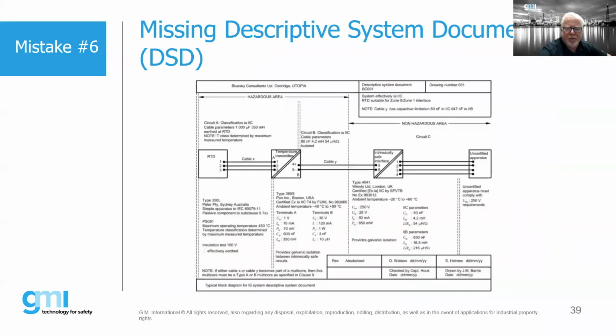And then finally, this is probably one of the biggest ones when we do an inspection on IS: we do not find a descriptive system document. I have done a significant portion of inspections on IS where I've asked the customer to provide me this information, and I get a look that is like, why? It's like I'm a unicorn or something like that. So the reason why this is important is that, as an inspector, when we follow the inspection charts that are published in 60079-17, that's one of the requirements.